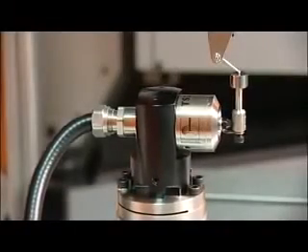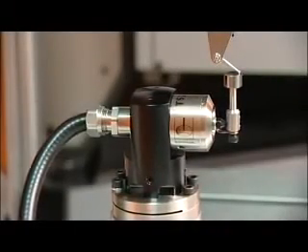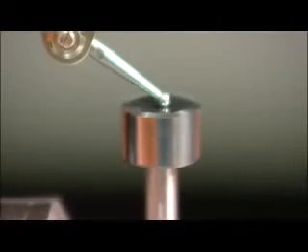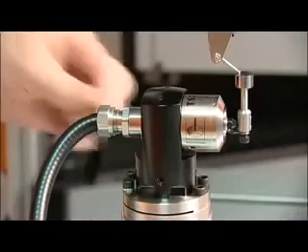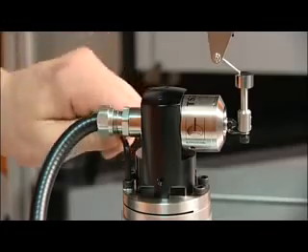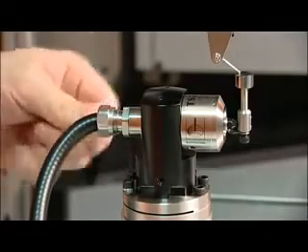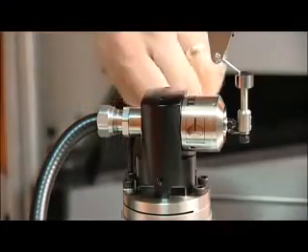The back to front error is adjusted out by rotating the cap head bolts. These bolts are opposing and lock against each other. Loosen one before tightening the other.